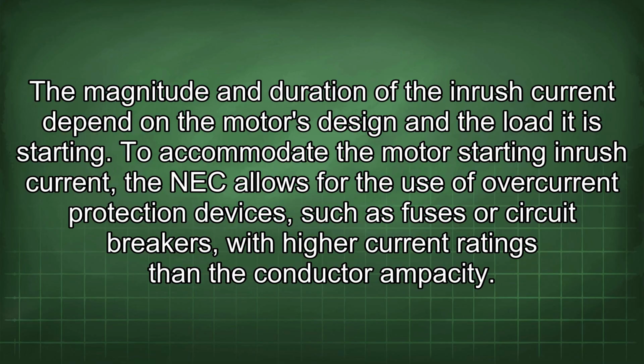To accommodate the motor starting inrush current, the NEC allows for the use of overcurrent protection devices such as fuses or circuit breakers with higher current ratings than the conductor ampacity.